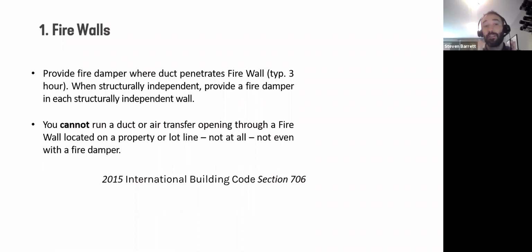Now, if you do penetrate a firewall, provide a fire damper. Typically, it's going to be a 3-hour fire damper. If you do have that structural independence where you have back-to-back walls, then provide a damper in each structurally independent wall.